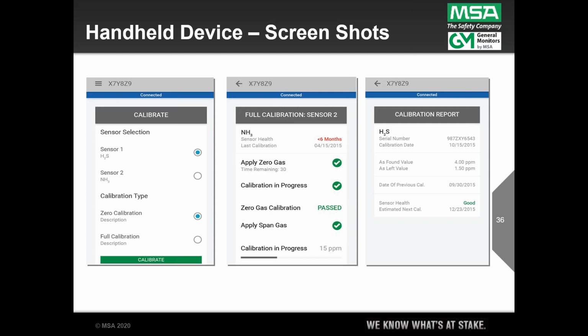And in some places, I know that outdoor sites, some of the technicians don't even get out of the pickup trucks to check their devices, and especially if they don't remember when they last did it. Well, now you can make communication with the devices, and it'll give you a report on when it was last calibrated. So that's pretty cool.